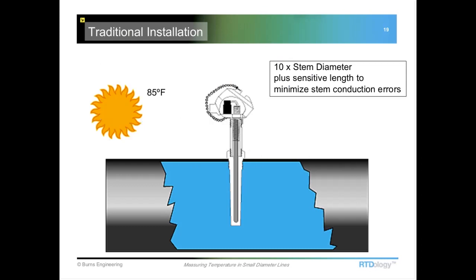Now, one of the big problems with small diameter lines is the stem conduction or immersion error. What is happening with this is that the temperature measurement is being affected by the ambient conditions. For example, if we have a process that's maybe running at, say, 121 degrees C, and our ambient conditions are, you know, room temperature, 20 degrees C, so we've got that delta of 100 degrees C difference.